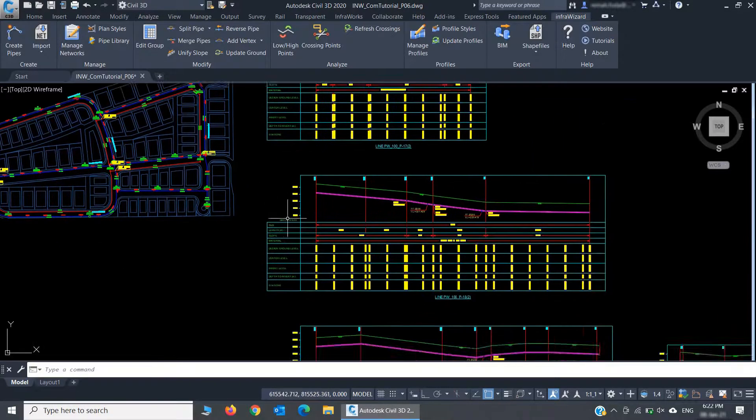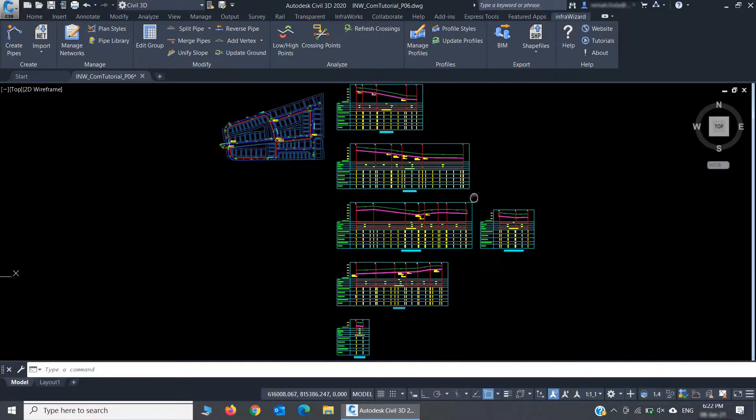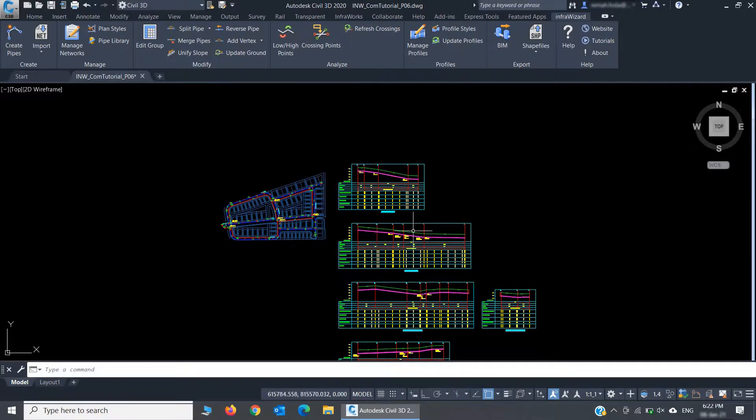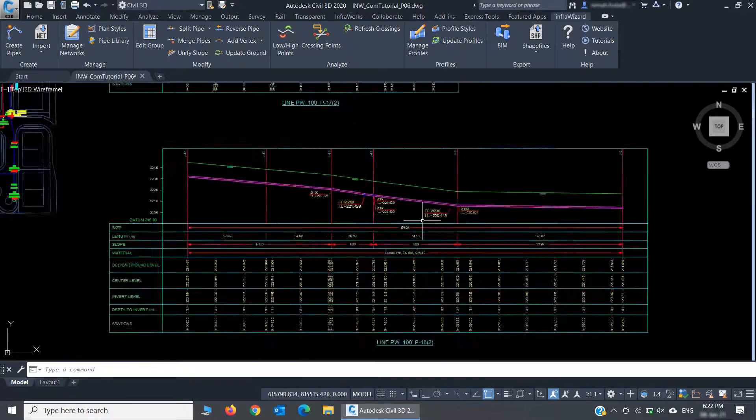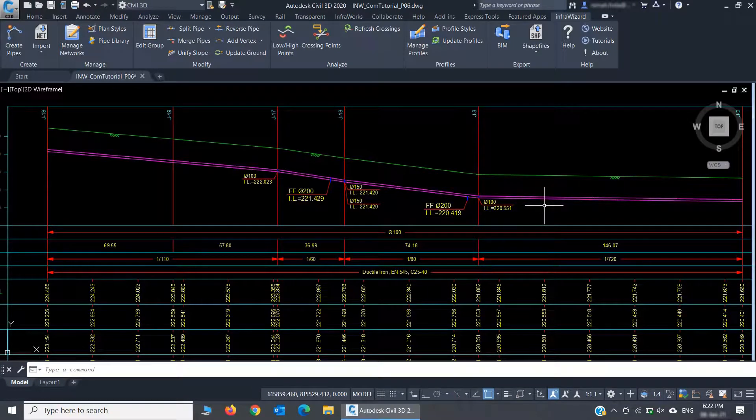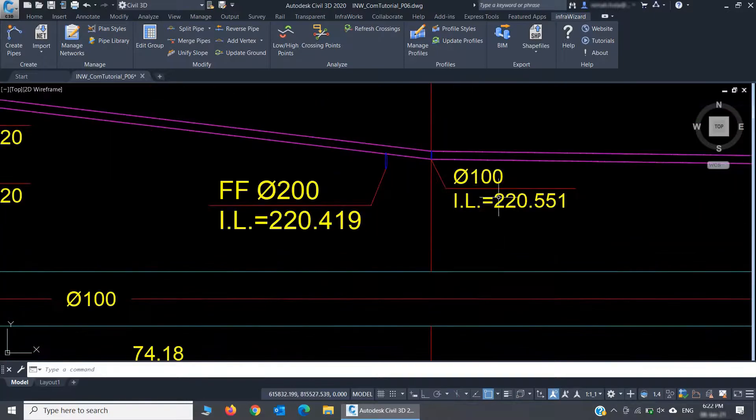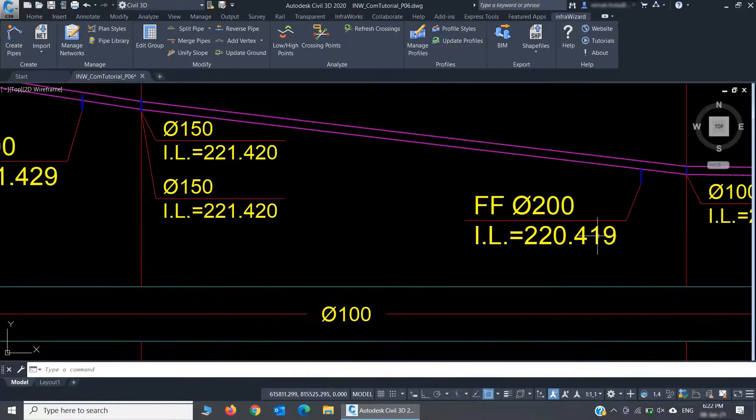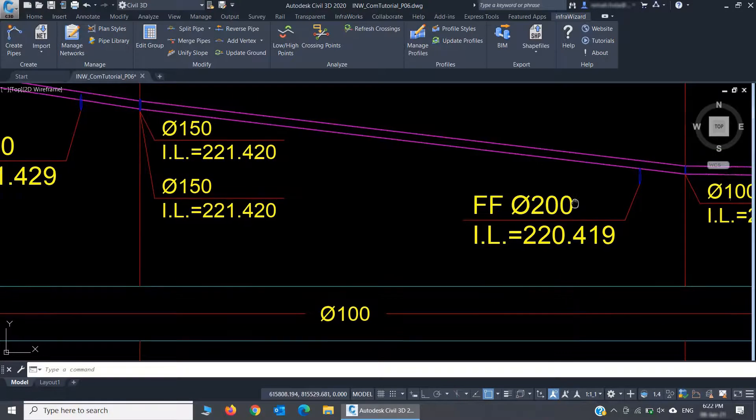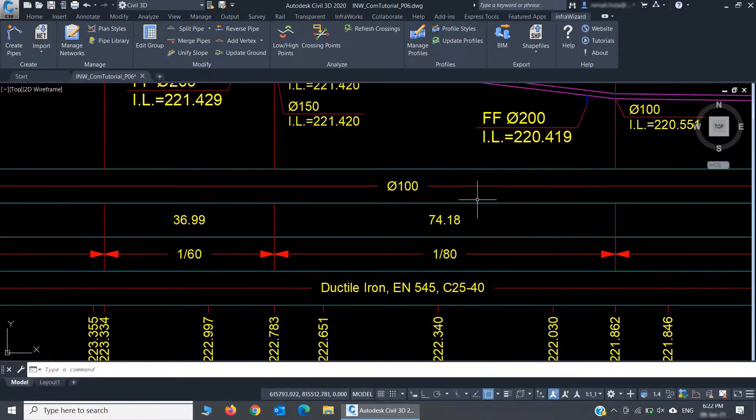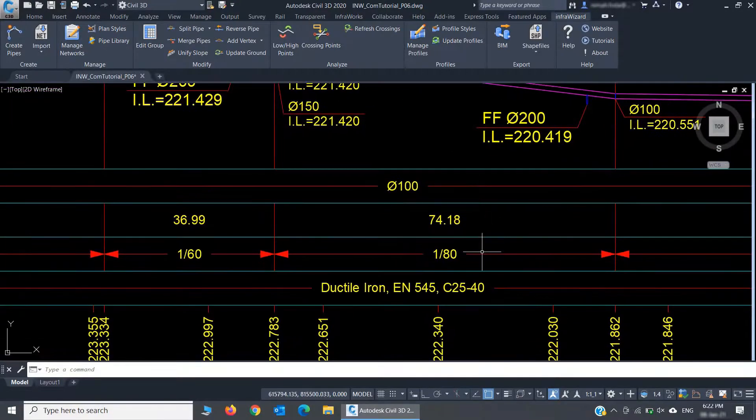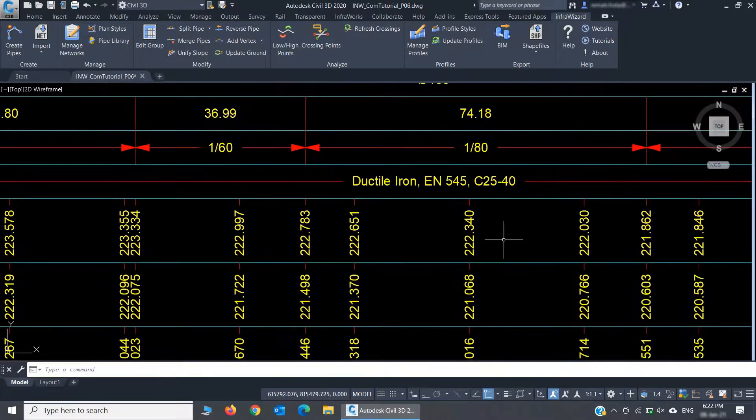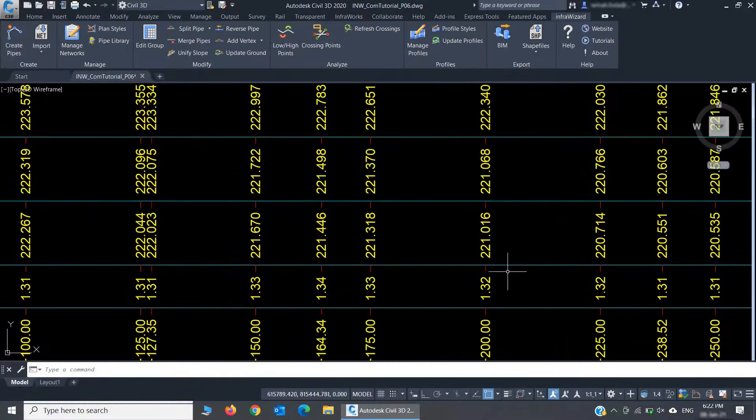Let's take a look at them. You can see here that the profile shows the main pipeline, the lateral pipes connected to it, and the crossing pipes of the other networks as well. The profile data bands include pipe diameter, length, slope, and material. It also shows the ground levels, invert levels, and other data.